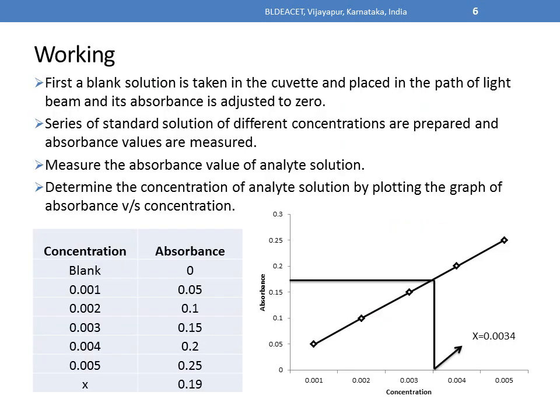Now we will see how the colorimeter works. In order to find out the concentration of an analyte solution, first we have to prepare a blank solution. The blank solution is a colorless solution, and using it we set the absorbance value to zero, because only colored solutions absorb light — since the blank solution is colorless, its absorbance value is set to zero. Then we prepare a series of standard solutions of different concentrations of the analyte and measure the absorbance value of all the standard solutions, and after that we measure the absorbance value of the unknown analyte solution.